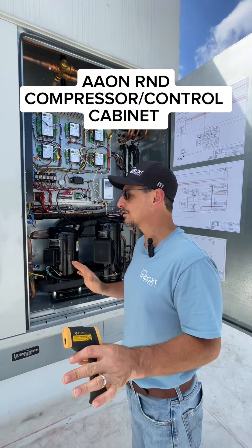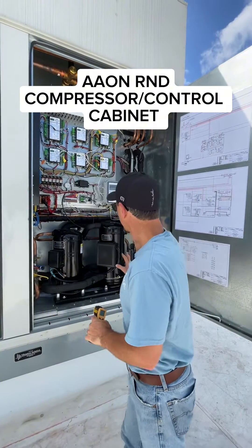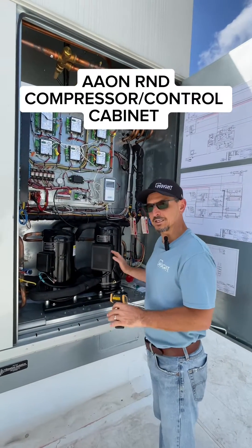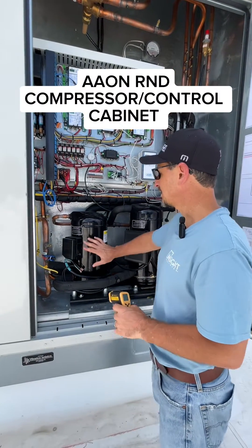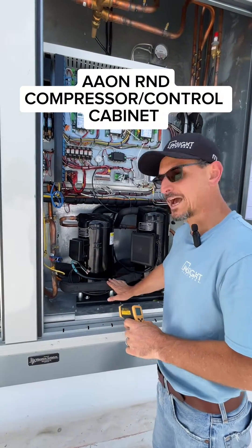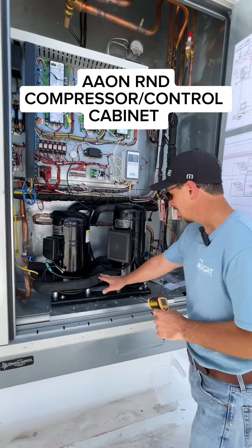So I wanted to walk you through the refrigeration cycle. This is a dual circuit, four compressor unit — typical arrangement for an AAON makeup air unit. I always like to start with the compressor, so the suction gas is coming into the bottom of the compressor here on both circuits.